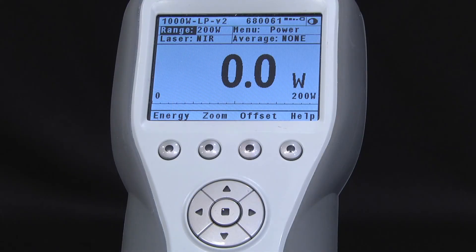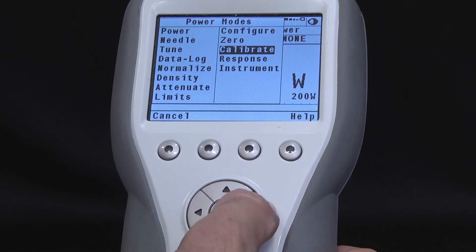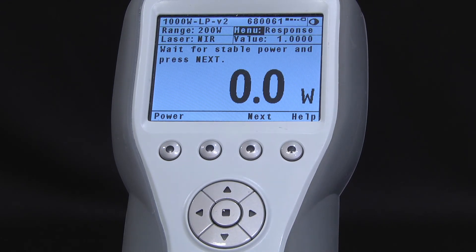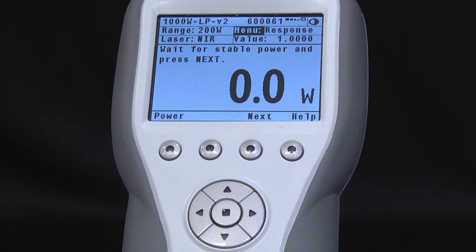There is one other type of factor related to the response time speedup function. This too can be user adjusted by going to Menu > Response and following the on-screen instructions to recalibrate the response time speedup. Modifying this factor incorrectly could cause the response time to slow down, or to speed up but with an overshoot or undershoot. In general, any modifications to factory-set calibration factors should only be done with the greatest of care, only if there is a real need, and only by qualified personnel.